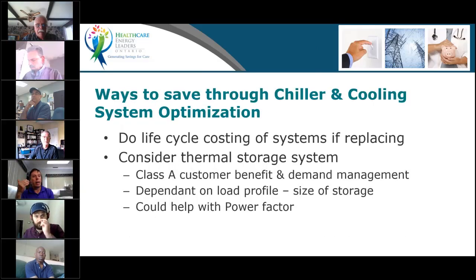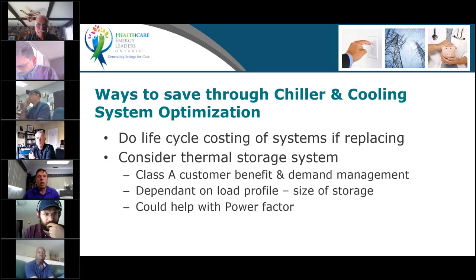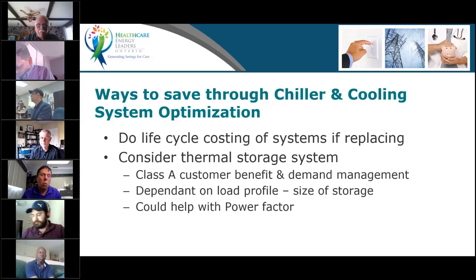And if you are a Class A customer and you really want to save, you could use thermal storage. Obviously, thermal storage is not a cheap solution, but if you already have the storage and it's not used, I've seen places where that was the case, or if you can use storage, you can significantly drop your demand during the 5 peak hours. Actually, you'll probably use it more than the 5 peak hours because you don't want to miss one of those hours, so you'll use it more often, but that's definitely something you'll do.